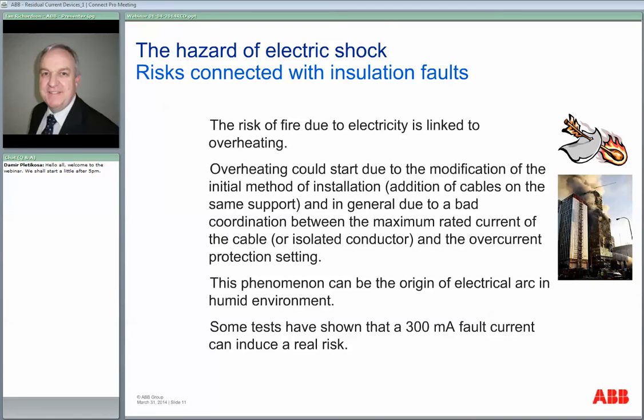So in general terms, on buildings, we'll be protecting somewhere in the order of about 300 milliamps. There are 100 milliamp RCDs available as well, which can be utilised there, and we go up in scale as well, normally by a factor of 3 depending on the products you might be using. So we'll go from our 30 milliamp to 100 milliamp to a 300 milliamp. There is actually a 500 milliamp, then go to 1 amp, 2 amp and 5 amp as we're getting higher up into the electrical network. It can be arranged in a very similar cascading principle that you might use for selectivity of circuit breakers.